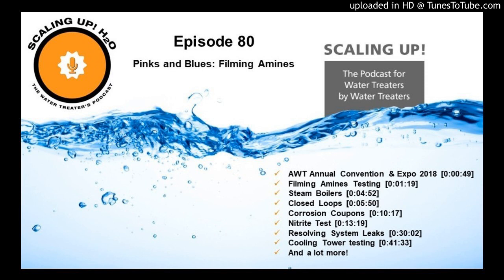Everything met that of the incoming water except for alkalinity. Alkalinity was a little bit high. It takes a while to flush all that through, but we were okay with that. With all the other ions out of the system, and pH and conductivity being really close, we decided that was flushed enough. And folks, whenever you flush a closed loop system, you've got to make that determination.